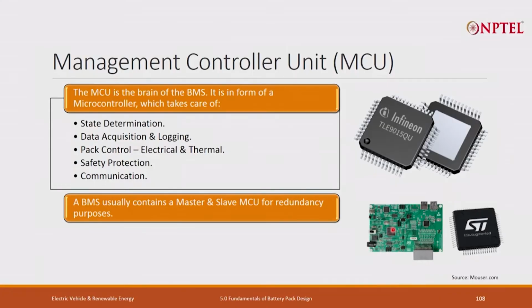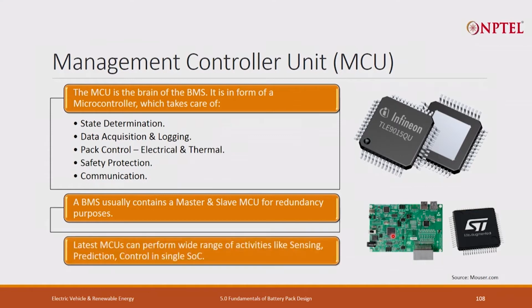In general, a BMS usually contains a master and slave MCUs for redundancy purposes. That's what we were talking about. If it is an integrated BMS, we can have one master MCU, and then we can have slave MCUs, which will take control if the master has failed. So the first level of protection comes from here. The second level of protection comes from here. The latest MCUs, like from ST or from Infineon, can do a lot of things together. They can sense, they can predict, they can control several devices in one go.